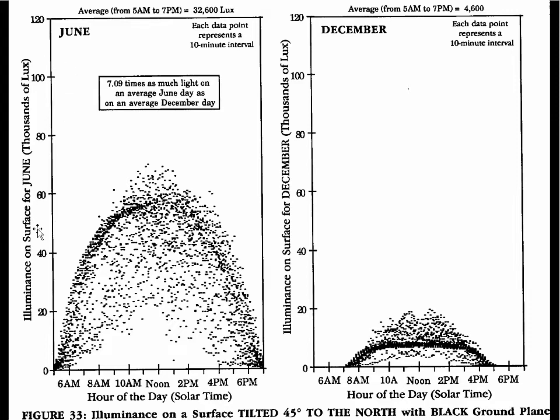Here is the daylighting data for that tilted north-facing aperture. We get lots of beam sunlight in June, and in December we get none whatsoever. The outlying data points represent times when there's a large bright white cloud in the northern sky, but the dense cluster represents the typical winter condition — not terribly bright, and not doing anything to offset the heating loads. During summertime when we have to cool the building, we have this fierce input of light and heat — the exact opposite of what we want from an aperture.